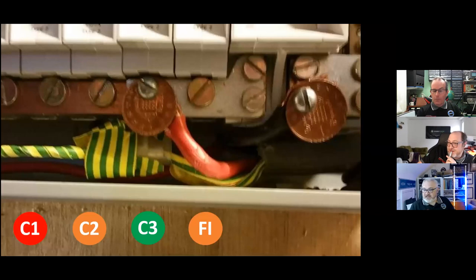So what's everyone saying on the chat? Majority are pushing C2 through. David says C2, but C1 if euros are used. Oh, just totally agree there. If it's a euro, it's a C1. Yeah, absolutely, completely agree. And he says if there's thermal effects, C1. So I kind of play devil's advocate in my mind when I look at coding. I go, okay, if I'm thinking it's a C2, what would I have to see to go to C1? What would I have to not see for it to be a C3? Just so that I can understand where I've come to my position.